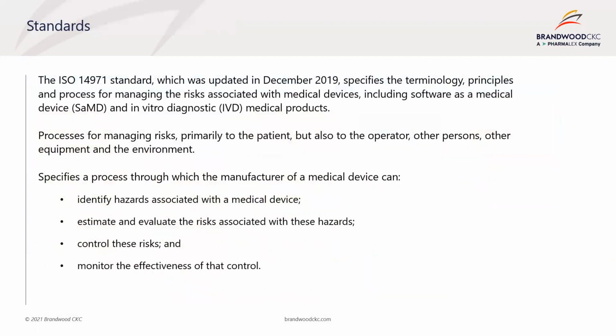Let's now explore further the standards in more detail. The primary accepted or harmonized standard internationally for risk management for medical devices is ISO 14971. It specifies the terminology, principles, and processes for managing the risks associated with medical devices, primarily to the patient, but also to the operator, other persons, other equipment, and the environment. It includes processes to identify hazards associated with a medical device, to estimate and evaluate the risks associated with these hazards, to control these risks, and monitor the effectiveness of the control. Importantly, it is applicable to all stages of the life cycle of a medical device.